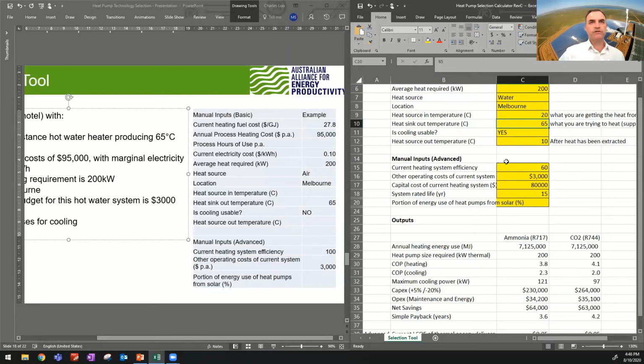Richard, you've got a client that needs chilled water applications, also has significant 75-degree hot water demands. Should a heat pump be considered? 75 sounds well and truly doable for a heat pump. That sounds like an ammonia job. If you need more chilled water, that heads it more towards a decision between ammonia and CO2.